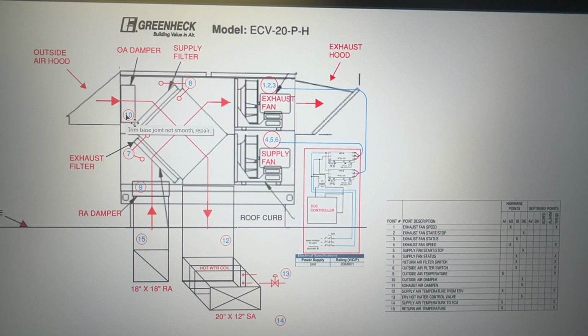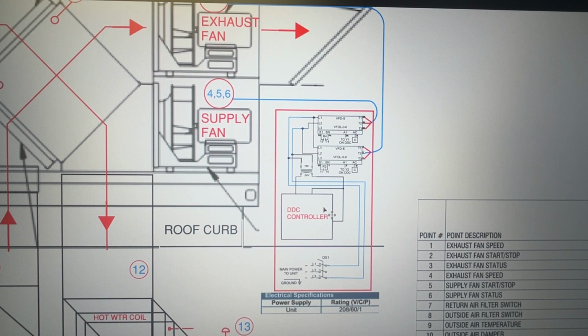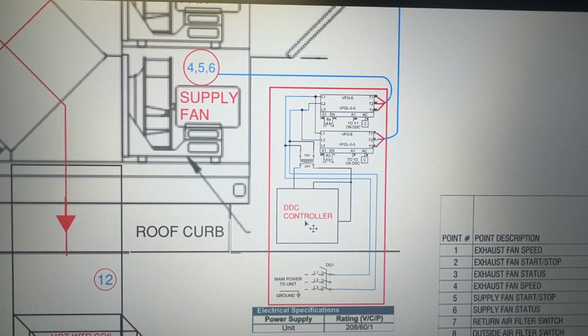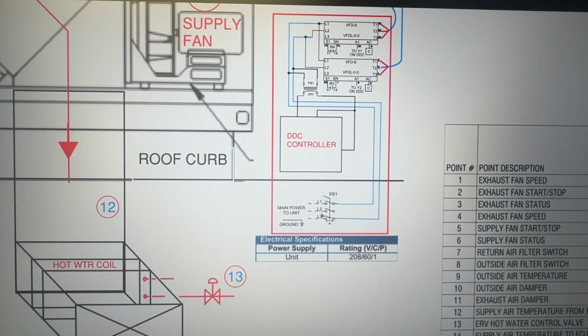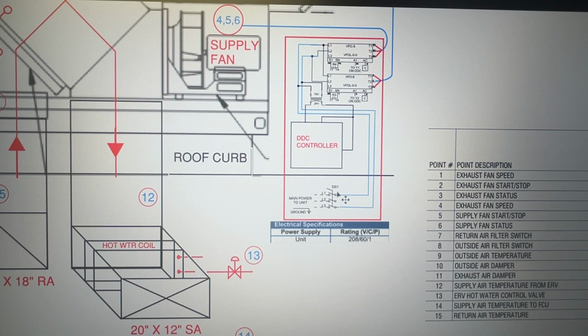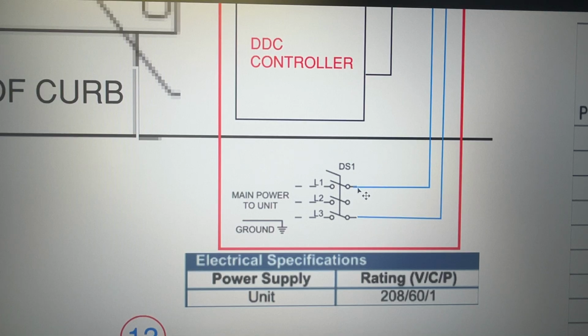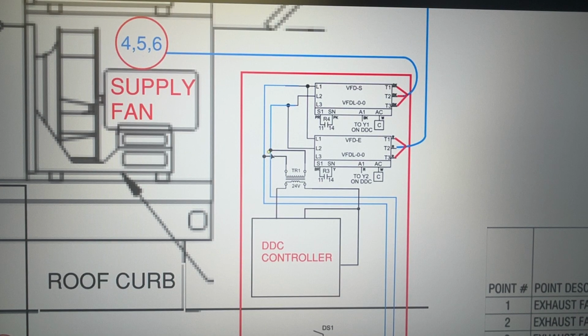So I'll start here at the top. Number 10 is our outside air damper. So that's going to be a control point. Let me pull in where the electronics are to this. The DDC controller controls this whole unit. So we first need to provide power from within the building up to this panel. That power goes to a disconnect with a ground. Then that power branches off to a transformer, brings it down to 24 volts, which goes to the DDC controller. And it also powers the two VFDs. So we have a VFD for our exhaust and a VFD for our supply.